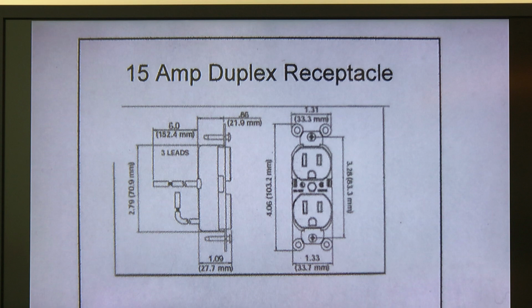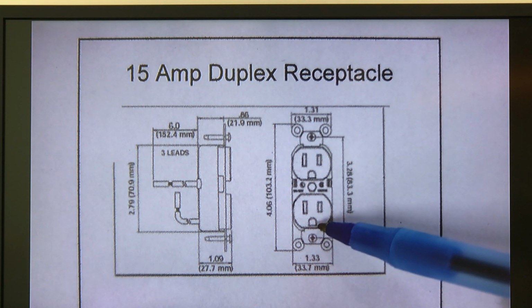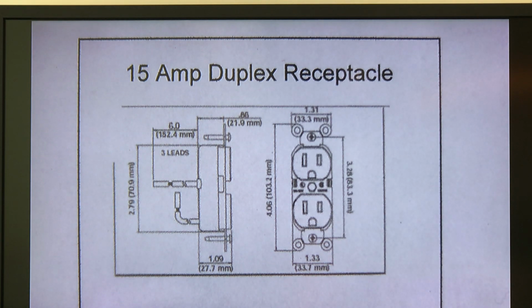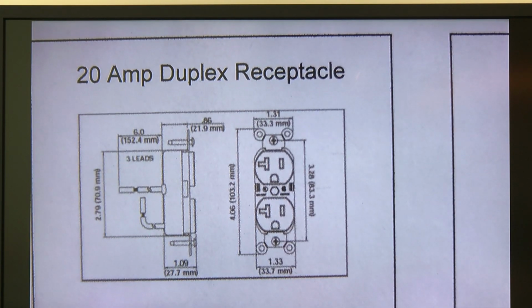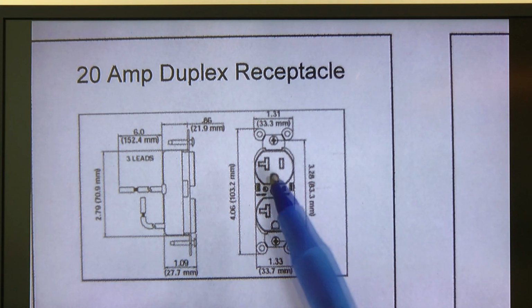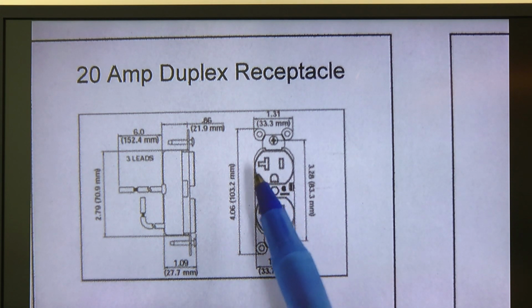That is because for a 15 amp duplex receptacle, we almost always will want the neutral connection to be bigger than the hot connection. The other one that you see down here, this little thing that looks like a mouth, that's the ground connection. Now in some cases, we don't have a 15 amp receptacle, but rather one for 20. And the arrangement is exactly the same. We have a hot connection over here, the ground here, but if you'll notice, you have a T-shaped object here for the neutral.